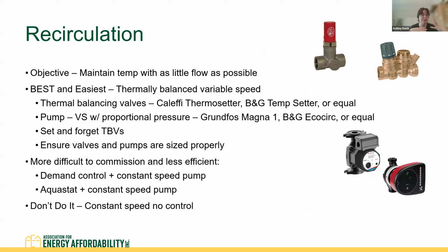Especially if we have a plant where we have a swing tank or like an electric resistance water heater doing the temperature maintenance. We want to make sure we're not just dumping tons of water into that tank all the time, because it's going to run too much and we're going to drop the efficiency of our plant. So the objective here is to maintain our loop temperature with as little flow as possible. The best and easiest way to do this is with a thermally balanced distribution system and a variable speed pump. This means installing thermostatic balancing valves on each of our risers or return loops, and then putting the pump in a pressure mode to react to those valves opening and closing.